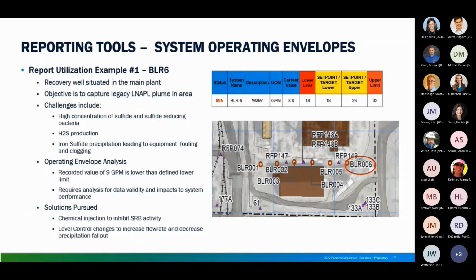Shown to the right on top is a cutaway of the operating envelope from one weekly data set that was collected off of BLR6. Beneath that is just an aerial shot indicating where exactly BLR6 is. The system's objective is to capture the legacy plume in the area, and some of the challenges related to it: there's a high concentration of sulfide and sulfide-reducing bacteria in this well that leads to a lot of H2S production, which is obviously a personnel hazard, but in particular for system operations, it leads to a lot of iron sulfide precipitation, which culminates in a lot of equipment fouling and clogging.